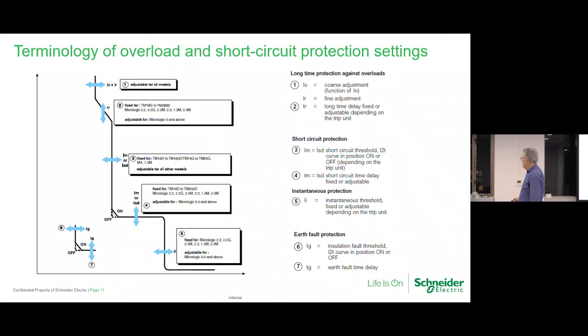And then all breakers, moulded case circuit breakers and ACBs, have instantaneous protection, but sometimes they don't have it as an adjustable element. It's just inbuilt in the breaker, so it reaches a certain amount of current and the thing will go out. That's very important that breakers are able to do that. And then we have earth fault that can be added in some more advanced trip units.